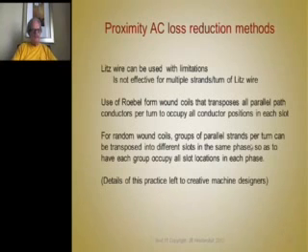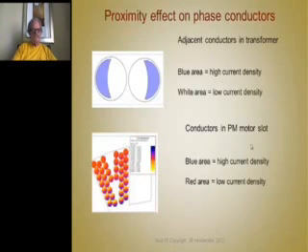It has to be used with limitations. It doesn't take care of proximity effects always. It depends. If every strand is transposed through the length of the core, then it does the same thing as a Roebel winding, which is a transposition method. Details of this practice are left to creative designers.